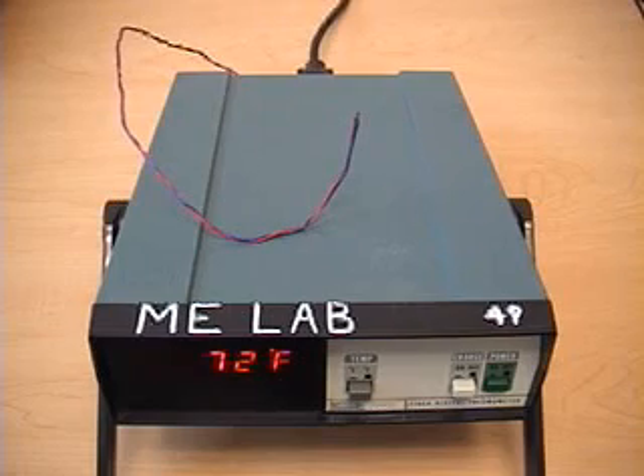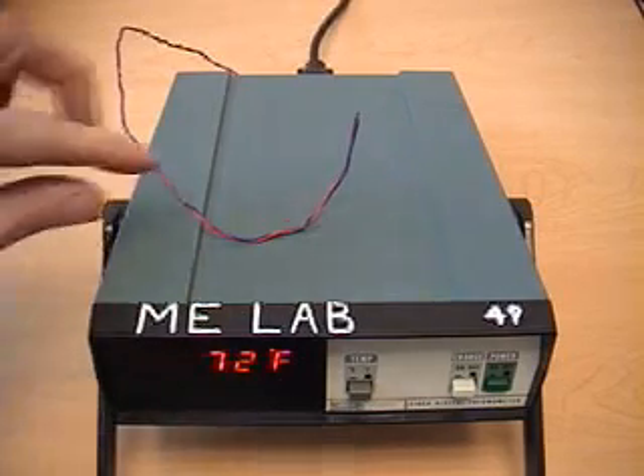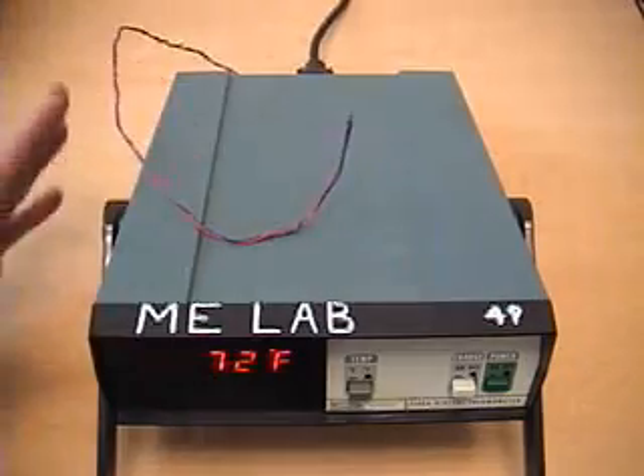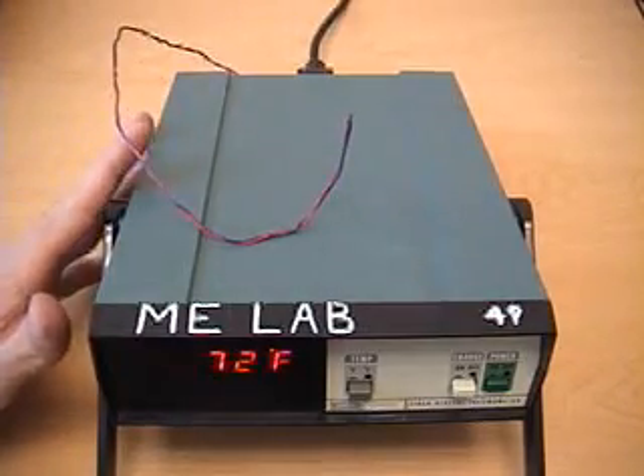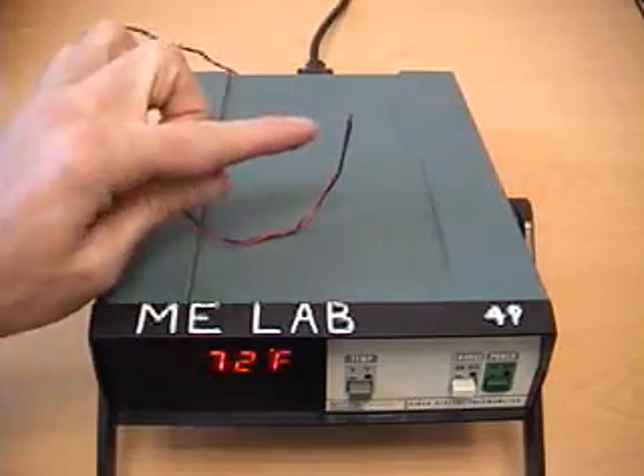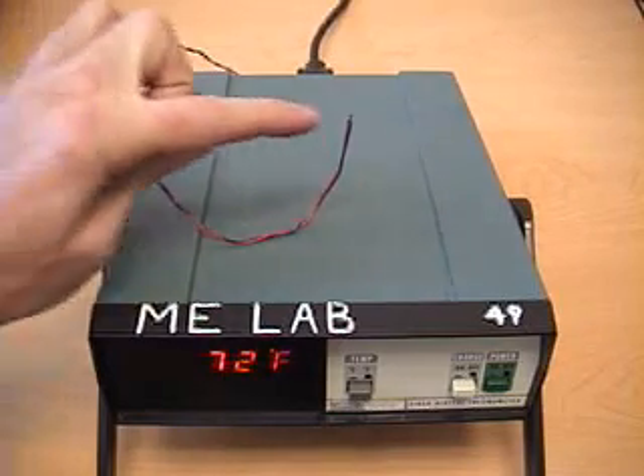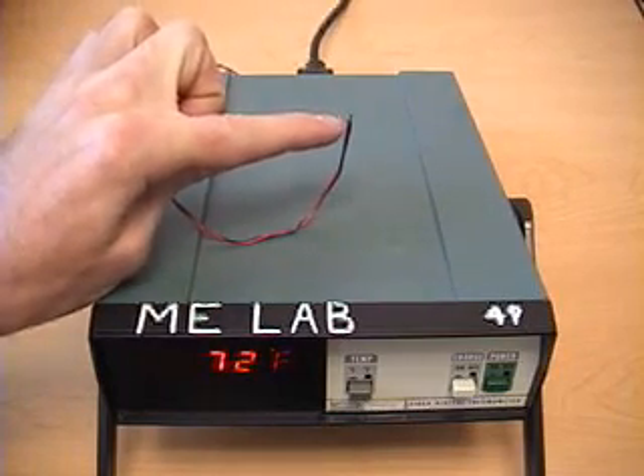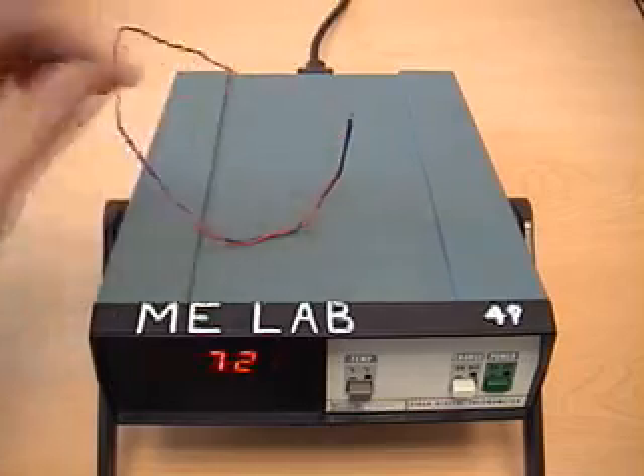This is a Fluke digital thermometer that can display temperature readings from a thermocouple. This particular instrument is configured for a Type T thermocouple, which uses copper wire and Constantan wire. The two wires are soldered or brazed together at the end, creating a measurement probe.